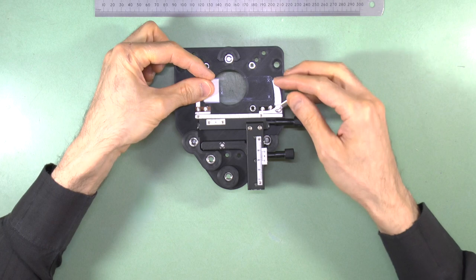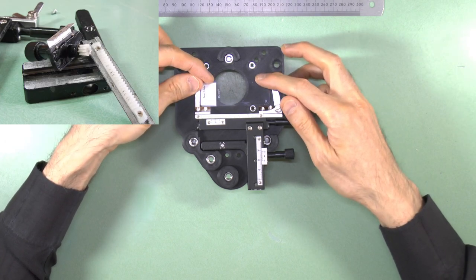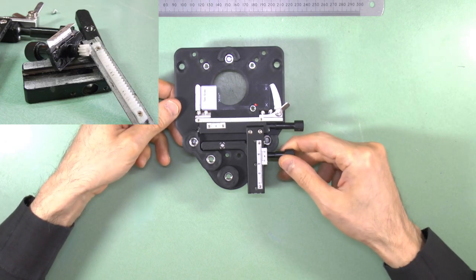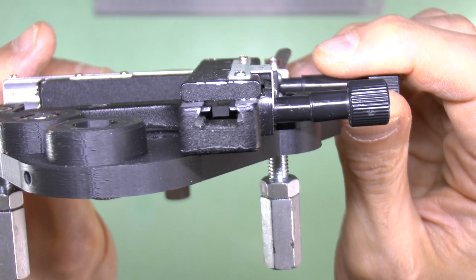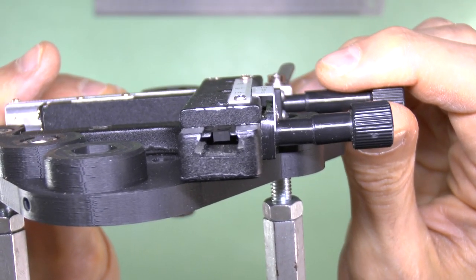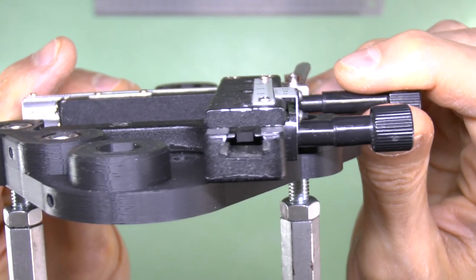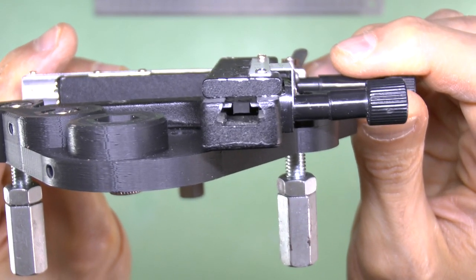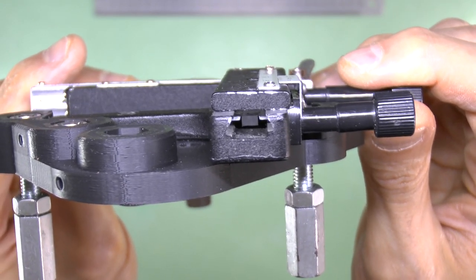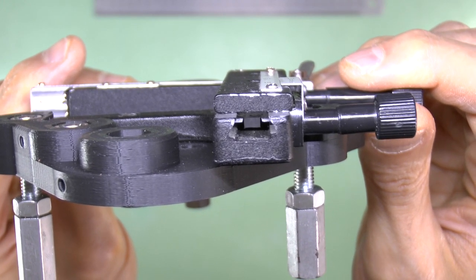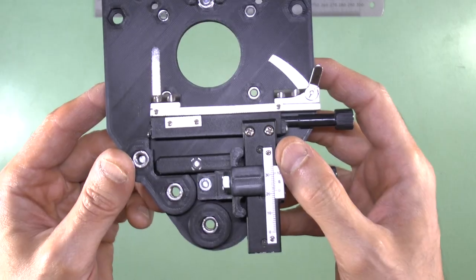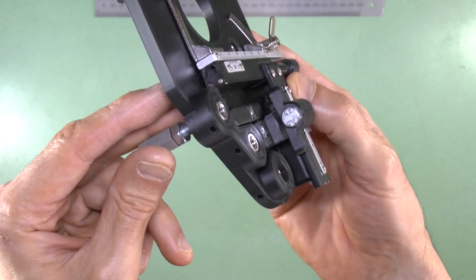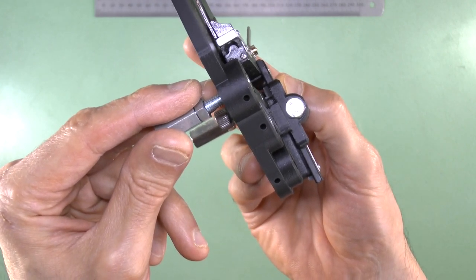Its limitations are that it has plastic gears that can get damaged more easily than metal gears. Some, but not all of them, also suffer from some lift of the X boom that can be distracting when moving a slide by hand, because each time you handle the X control, the slide can go out of focus. The Puma XY stabilizer module, discussed later, was designed to reduce this lift.